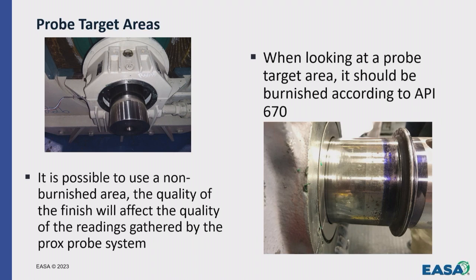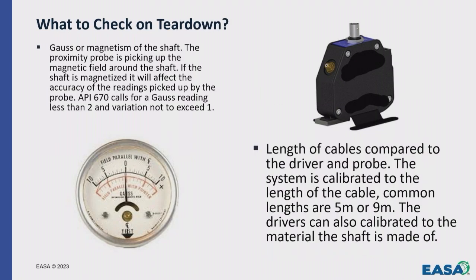And then if you look at the picture on the right, that would be an area that's not so good. Every one of those dings, dents. Keep in mind, we're measuring in mils, which is 1,000th, when we're looking at this vibe data. So if you've got a nick, even if it's only a 0.5 deep, you're already going to be reading a 0.5 mil, even at slow roll. So you've got to think about how well that needs to be finished. And then API 670 is just one of the standards that talks about that. There's a few out there.